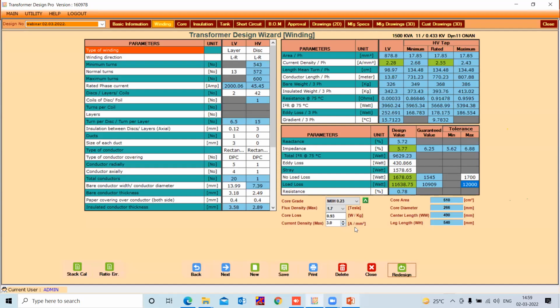Now, friends, I draw your attention to the extreme right and bottom. You are in a position to see some information related to the core. The core area, 510 centimeters square. Core diameter, the center length, that is the window width. You can see the leg length, that is window height. Now, let me take your attention to the left-hand side column, my left-hand side table. It has 4 columns. The first being the parameter, second being the unit, third being the LV winding, and last column being the HV winding.